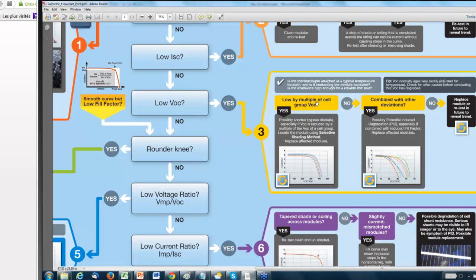Our first question is to look at the VOC we measured compared to all the others in the strings measured at that combiner box, and pay attention to the spread. If all the strings are gathered together in a tight group of VOC values, but there are 1 or 2 strings that are 10 or 12 volts below that, or multiples of that, maybe 20 to 24 volts below, those are good indicators.